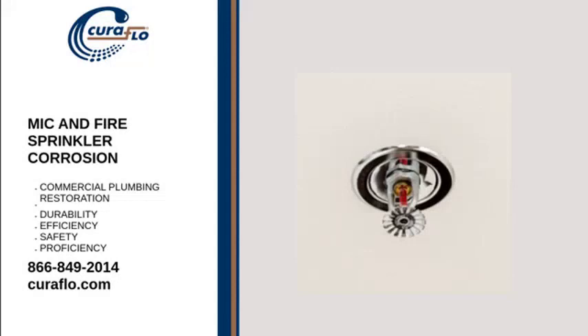NFPA 13 specifies that when conditions are found that contribute to MIC, the owner should notify the installer of the sprinkler system and develop a plan to treat the system with one of these methods: installing water pipes that won't be affected by MIC microbes, using approved biocides to treat all water entering the system, implementing a plan to monitor the pipe's interior condition at specific locations and time intervals, and installing a corrosion monitoring station to monitor at specific intervals. Epoxy pipe lining is one of the approved methods that can be used to prevent MIC corrosion. NFPA 25 also specifies how water-based fire protection systems should be inspected, tested, and maintained.